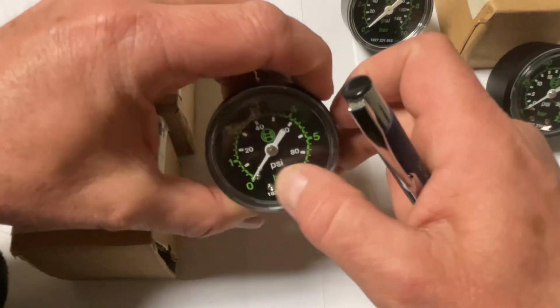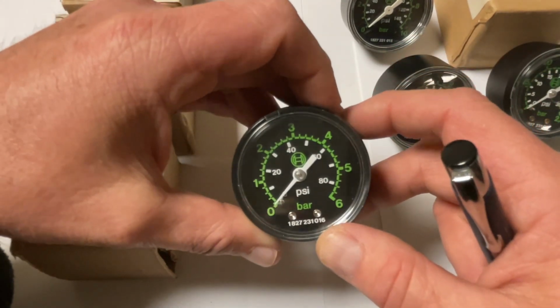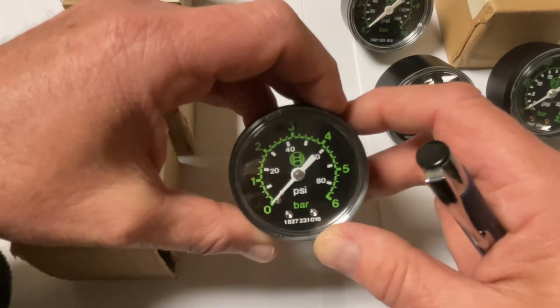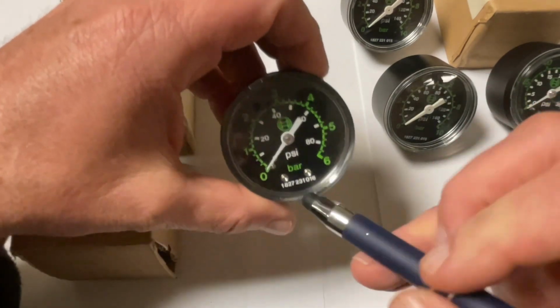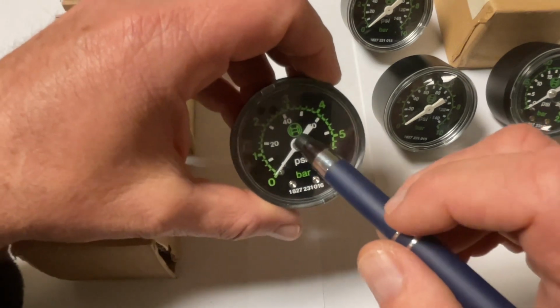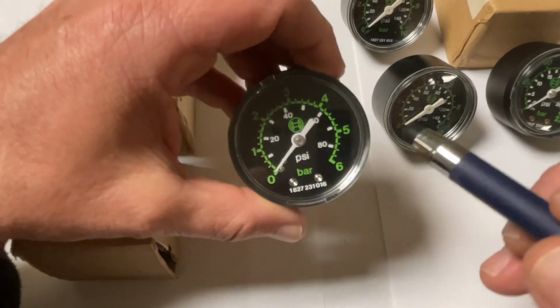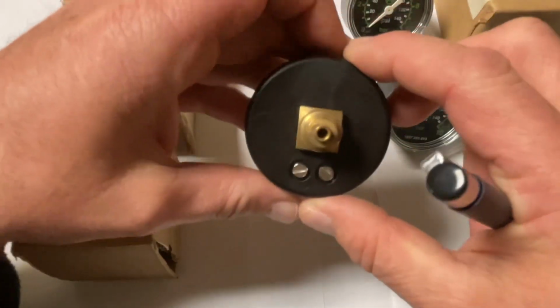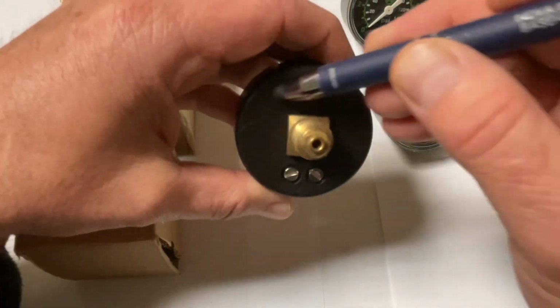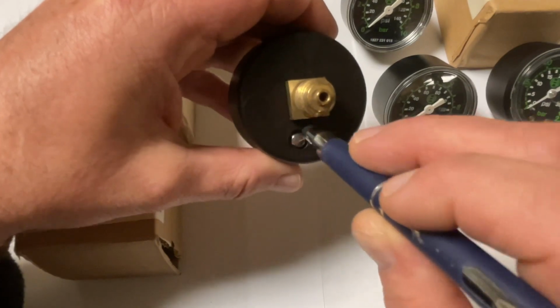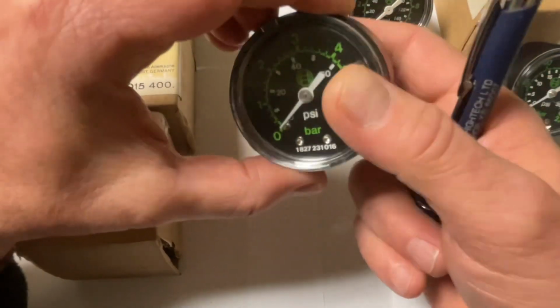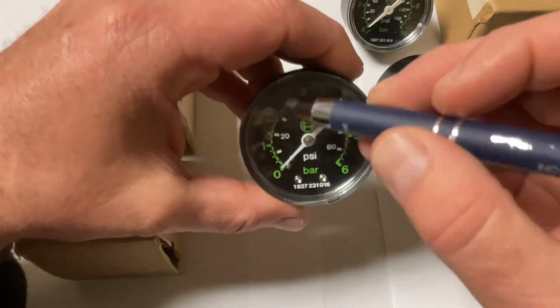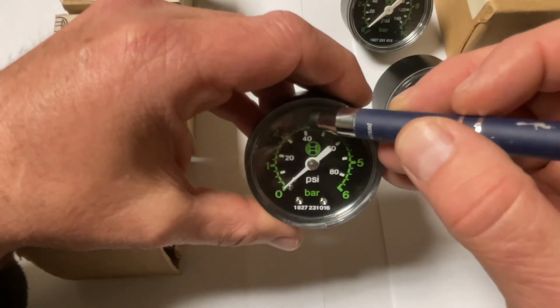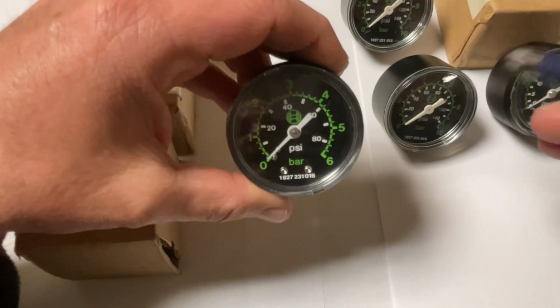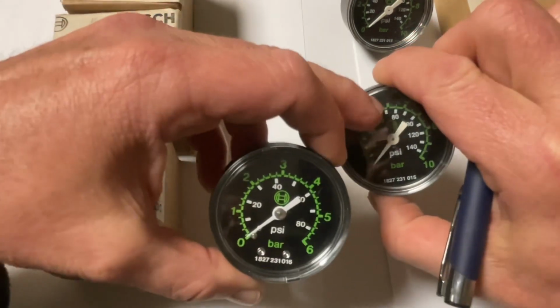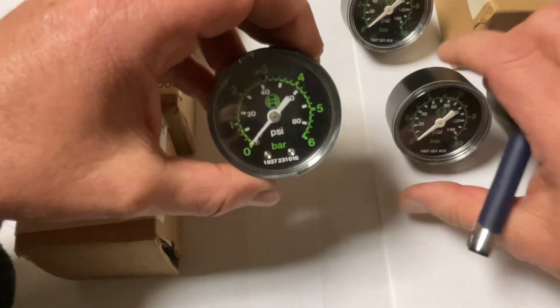The way you can identify the authenticity of a Bosch made for internal use only gauge is by the numbers, by the green Bosch sign in here, PSI and bar for both. And they have 2 screws where you can take this out, and there is a calibration set screw in there where they can be actually calibrated. And the way they are calibrated is you apply a known source of the pressure at the center mark of the scale, in the center of the scale, and then you can adjust this.